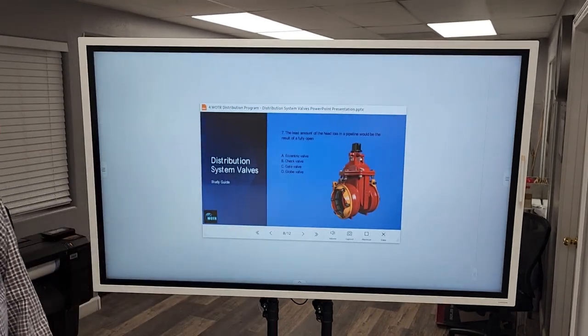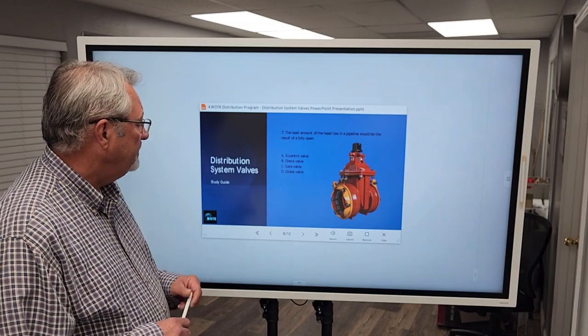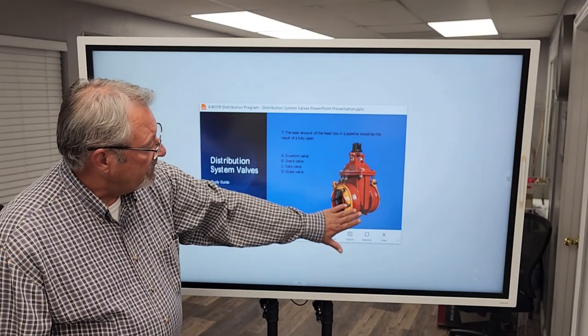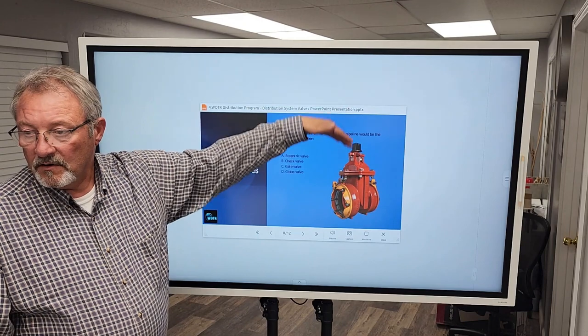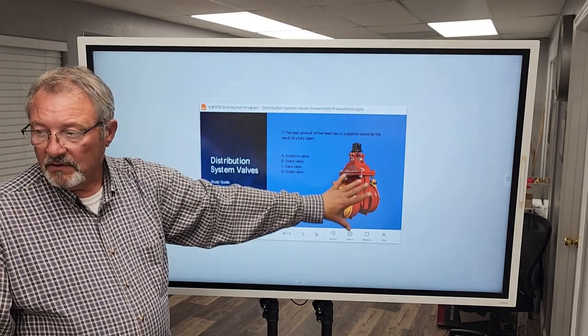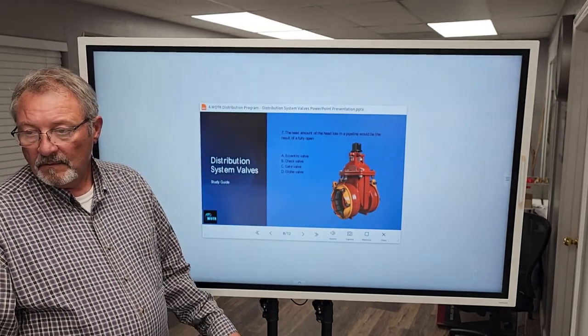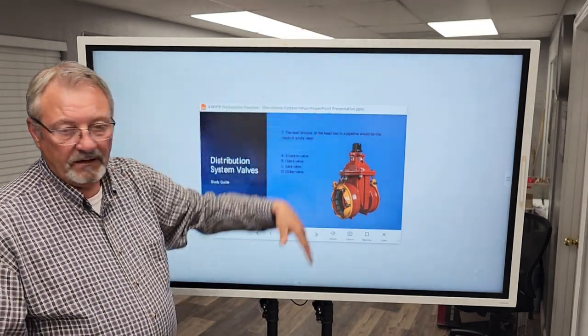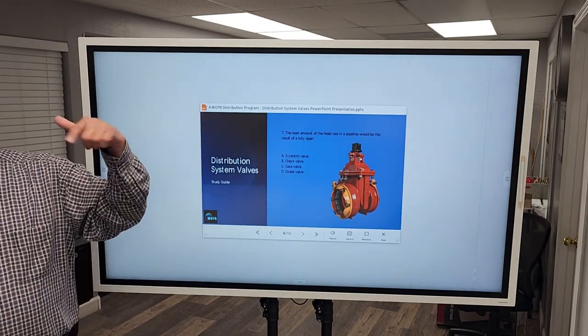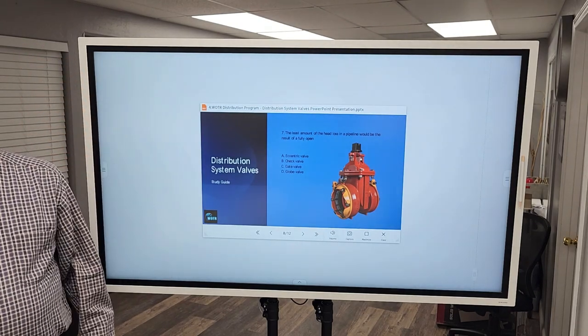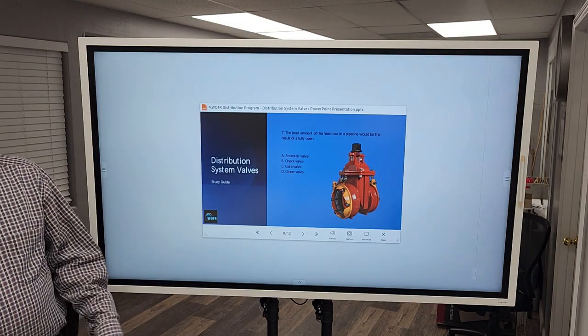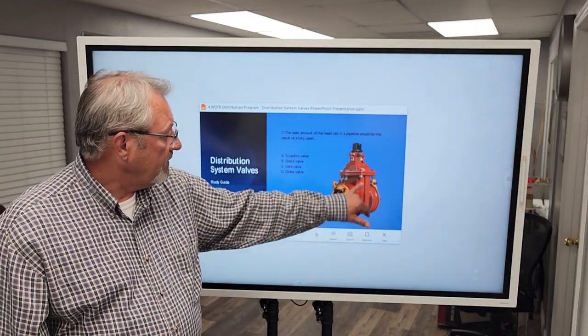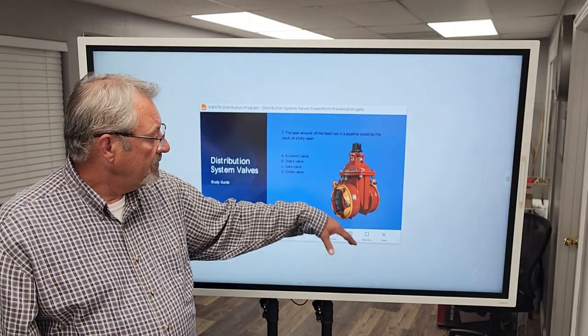Number seven, the least amount of head loss in a pipeline would be the result of a fully open gate valve. That gate moves up and down. This is the operating nut. You can have a rising stem or a non-rising stem. When the gate valve or the valve is below grade, below ground level, you want a non-rising stem. A non-rising stem is one that won't rise up outside or these types of valves that are outside and above ground. Very often you'll see a rising stem, so you have a long stem that's on a gate and you can actually see it through sight glass. You can see the stem moving up and down as the gate opens and closes. Inside here we have the large gate and that gate will slide up and down to open and close.